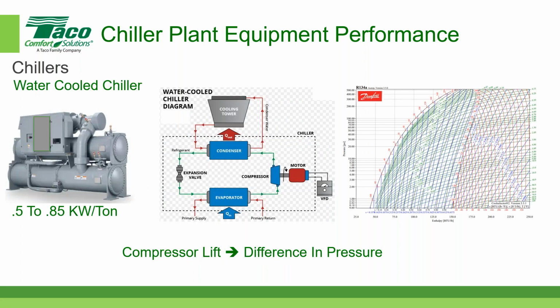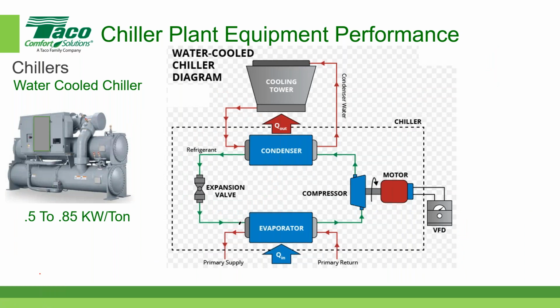All right, let's look very briefly at what affects the efficiency of a chiller. On the left side is our water-cooled chiller. In the middle, we have a very simple refrigerant diagram for a water-cooled chiller, which also includes the cooling tower, and also where we have the primary chilled water. I'm going to go into a larger diagram so you can see it. We're also going to talk a little bit about the pressure enthalpy diagram. This is a pressure enthalpy chart over here, and I want to point out that this is for refrigerant R134a, which is a very popular refrigerant used today. So let's go to the next slide and focus on the refrigerant cycle as it pertains to a water-cooled chiller.